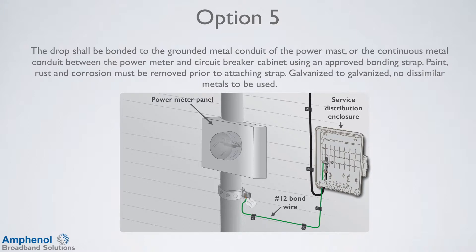With option number 5, the drop is bonded to the grounded metal conduit of the power mast, or the continuous metal conduit between the power meter and the circuit breaker cabinet, using an approved bonding strap. If attaching to the conduit on the home side of the meter panel, make sure the conduit is metal and is continuous to the circuit panel box. Use the proper clamp manufactured for copper contact on one side and galvanized pipe on the other. Make sure the contact point is clean of corrosion and paint prior to attaching the strap. The power mast cannot be used as a drop attachment to gain height over driveways, sidewalks, or streets. It's also good practice to add a do-not-remove tag. Always follow your company's installation practices.